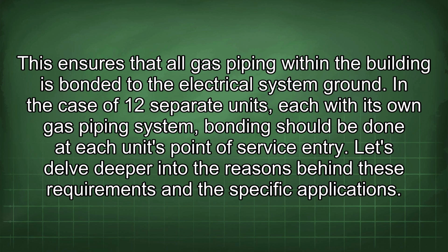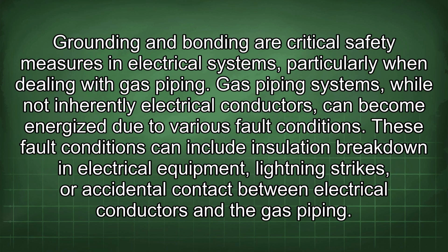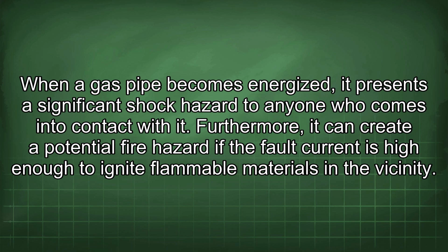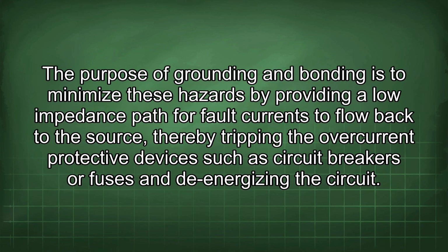Let's delve deeper into the reasons behind these requirements and the specific applications. Grounding and bonding are critical safety measures in electrical systems, particularly when dealing with gas piping. Gas piping systems, while not inherently electrical conductors, can become energized due to various fault conditions. These can include insulation breakdown in electrical equipment, lightning strikes, or accidental contact between electrical conductors and the gas piping. When a gas pipe becomes energized, it presents a significant shock hazard to anyone who comes into contact with it. Furthermore, it can create a potential fire hazard if the fault current is high enough to ignite flammable materials in the vicinity. The purpose of grounding and bonding is to minimize these hazards by providing a low impedance path for fault currents to flow back to the source, thereby tripping the overcurrent protective devices such as circuit breakers or fuses and de-energizing the circuit.